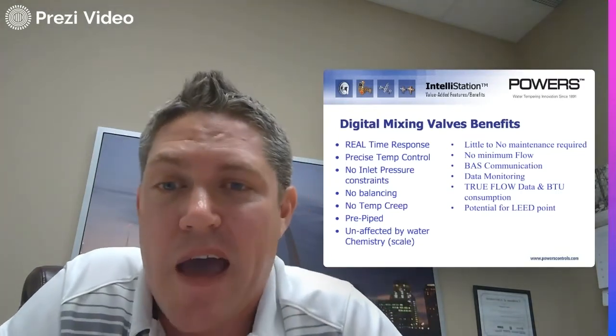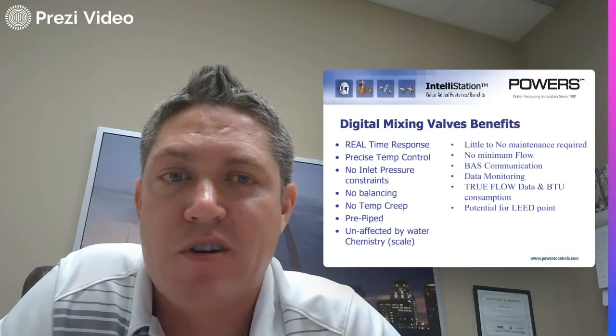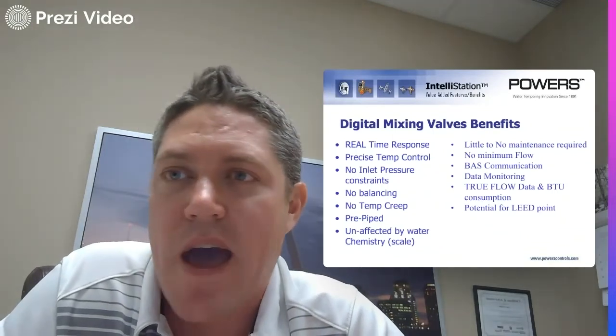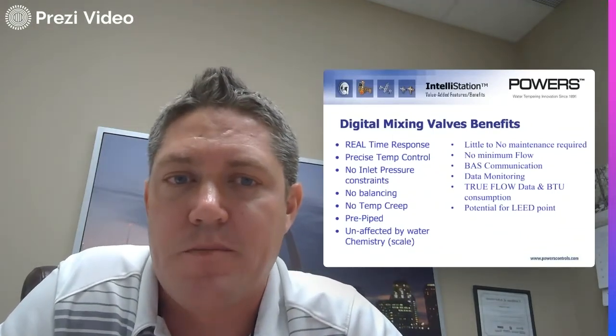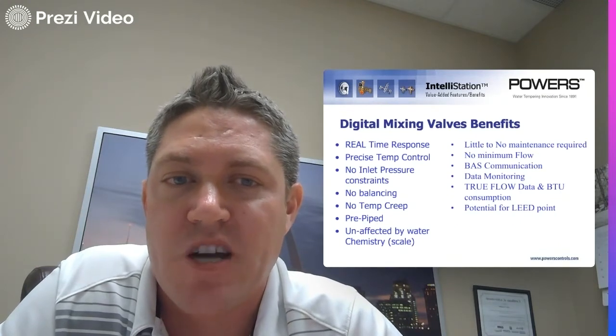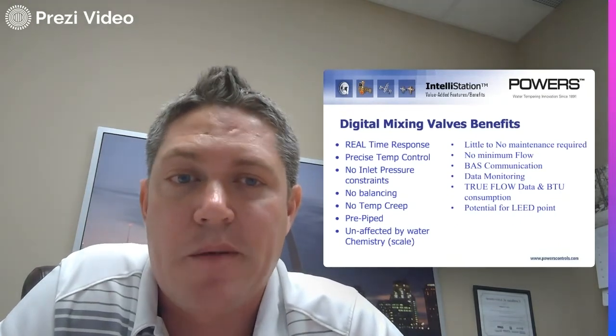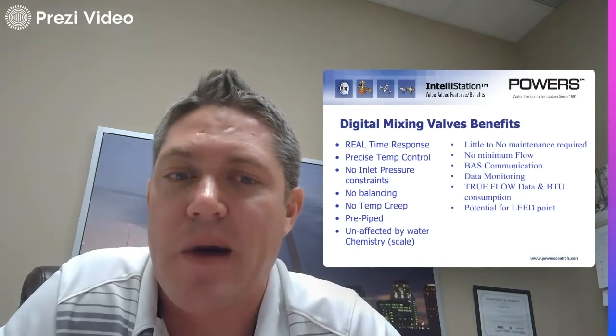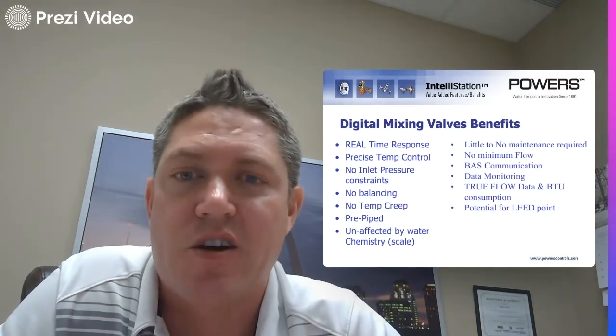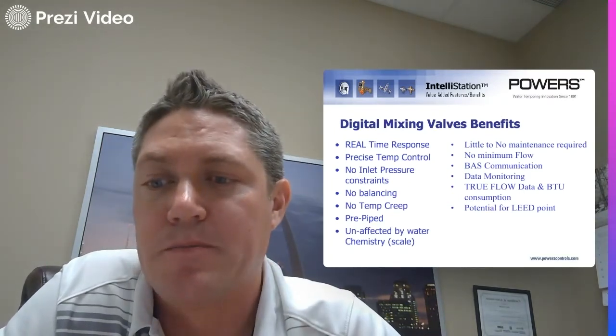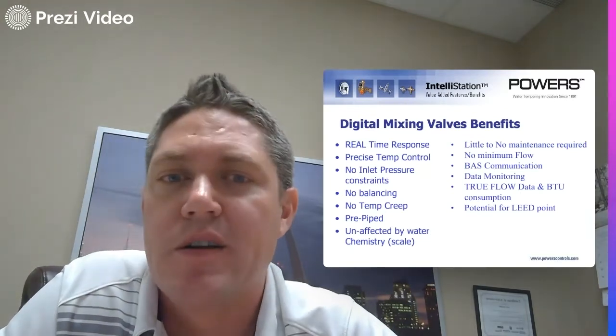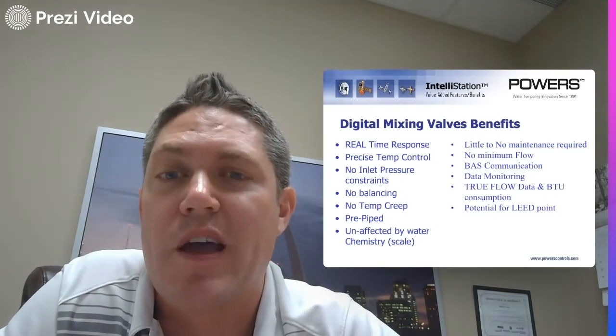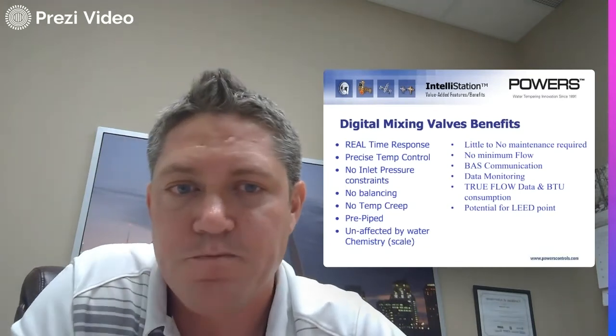They're BAS compatible. That comes standard on the Powers digital mixing valves. No added module or anything like that. They're BAS capable from the jump, which helps with the data monitoring. A bunch more data monitoring points: temperature, pressure, hot, cold, mixed, return. So that data really helps for troubleshooting when there is an issue.